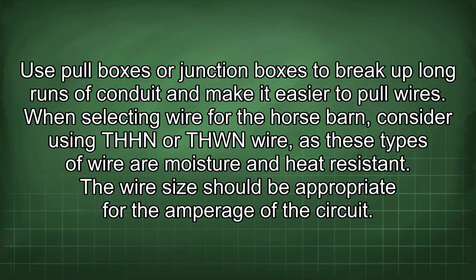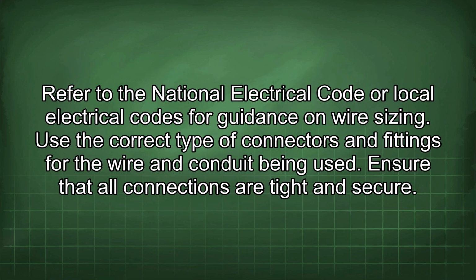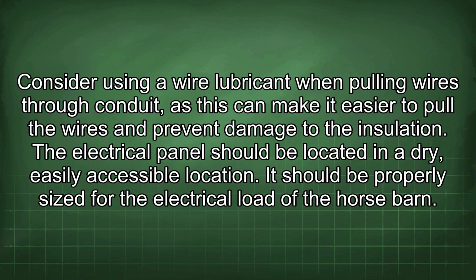easier to pull wires. When selecting wire for the horse barn, consider using THHN or THWN wire, as these types of wire are moisture and heat resistant. The wire size should be appropriate for the amperage of the circuit. Refer to the National Electrical Code or local electrical codes for guidance on wire sizing. Use the correct type of connectors and fittings for the wire and conduit being used. Ensure that all connections are tight and secure. Consider using a wire lubricant when pulling wires through conduit, as this can make it easier to pull the wires and prevent damage to the insulation.